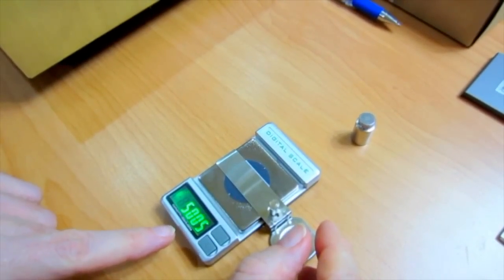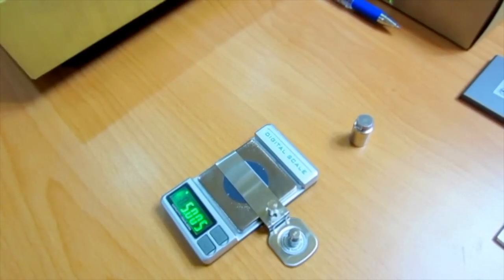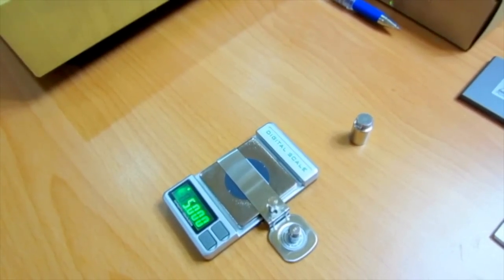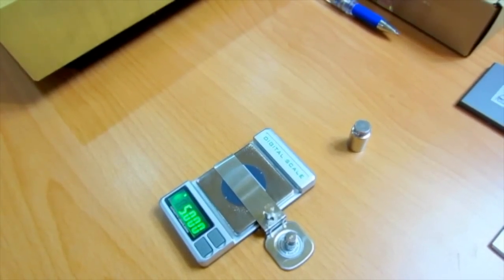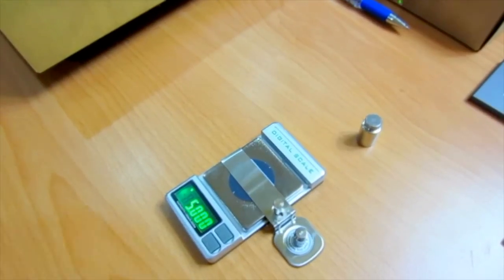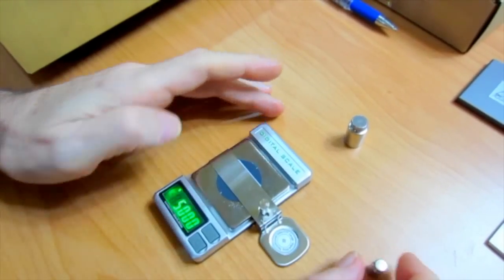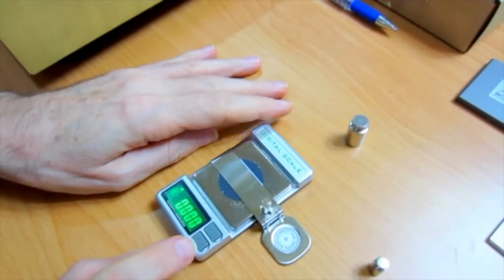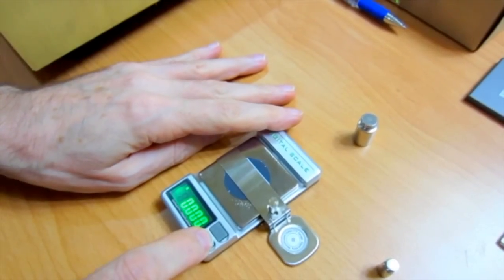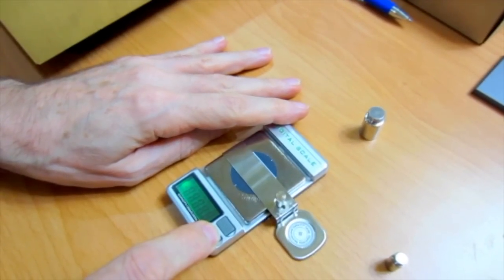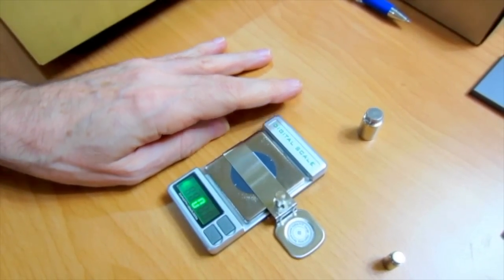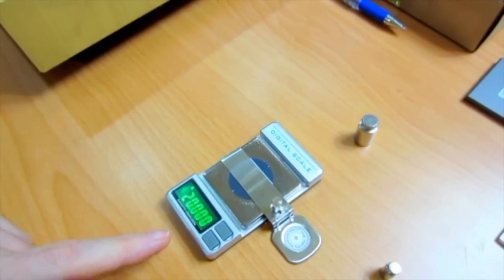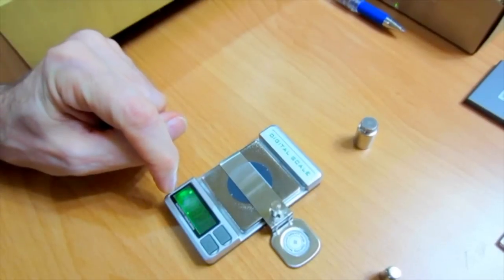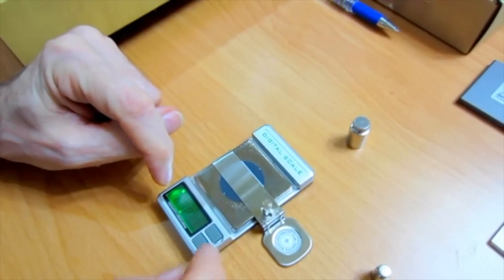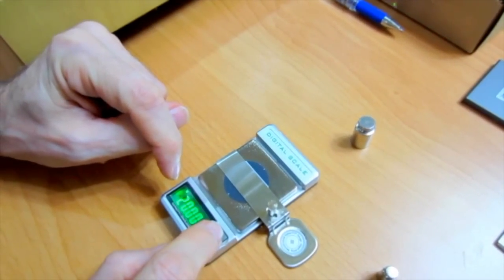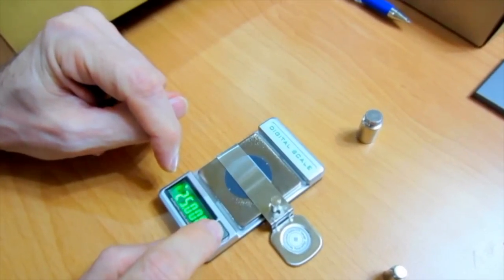Let's suppose we were reading outside the readability, which is 0.005. Let's suppose we read 5.02. We want to recalibrate. Let's go through that procedure. It's very quick with this scale. What you'll do is you'll press the on-off button, hold it down until you see a single 0. Release. Now you're going to wait until this flashes. This was previously calibrated for 20 gram mass. Now what we're going to do is press the unit button. We want to get to 5.